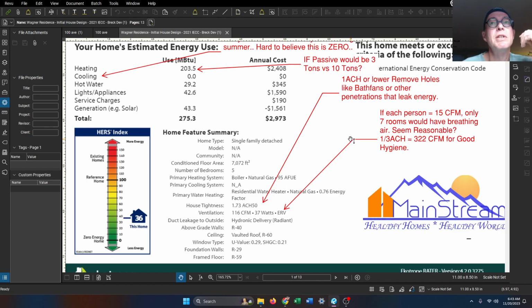Speaking of which, ventilation jumps out at me too, because for 7,000 square feet, it's only calling for 116 CFM. So what is our objective with ventilation? I believe it's human hygiene, and that's why ASHRAE came up with the formula of 1/3 air change per hour for good hygiene, which comes out to 322 CFM alone.